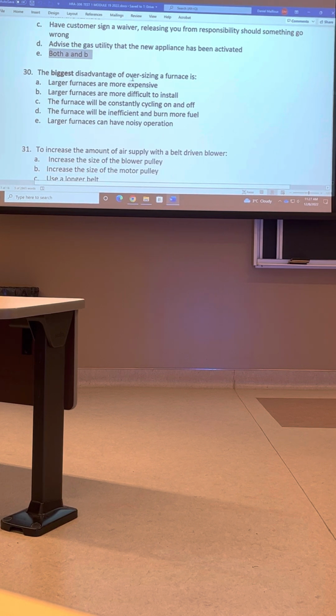The biggest disadvantage of oversizing a furnace is the furnace will be inefficient and burn more fuel. All right, so it's going to cost you more to operate a bigger furnace. It'll run very inefficiently. The difference between an 80,000 BTU furnace and a 100,000 BTU furnace is like $40.